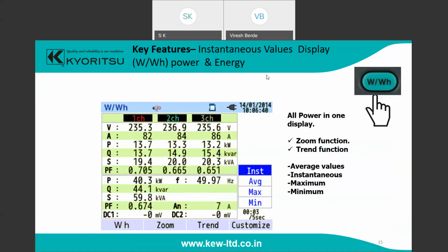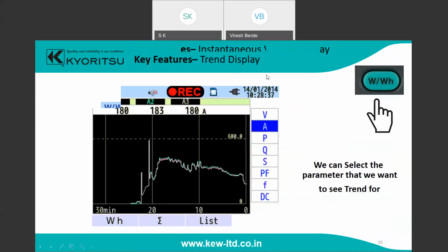Another key feature is you can show the trend display also. You can just show the trend display for ampere only, or with all phases. Just use the function switch, select the ampere function, and you can show ampere as well as voltage, power, power quality, and PF of each phase. If connected to a DC supply, you can check the DC power also.